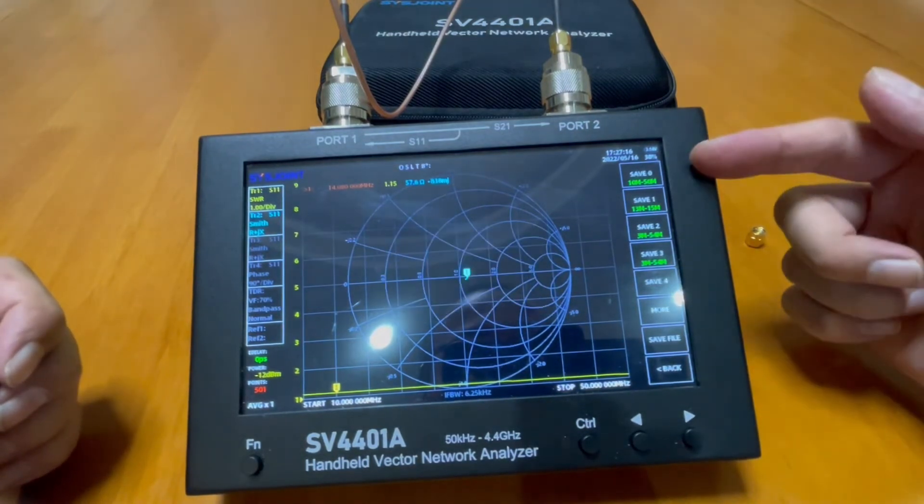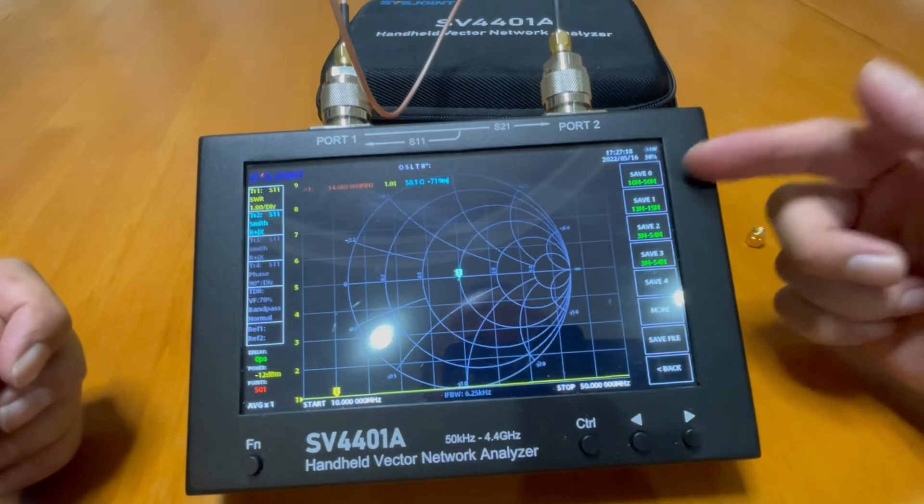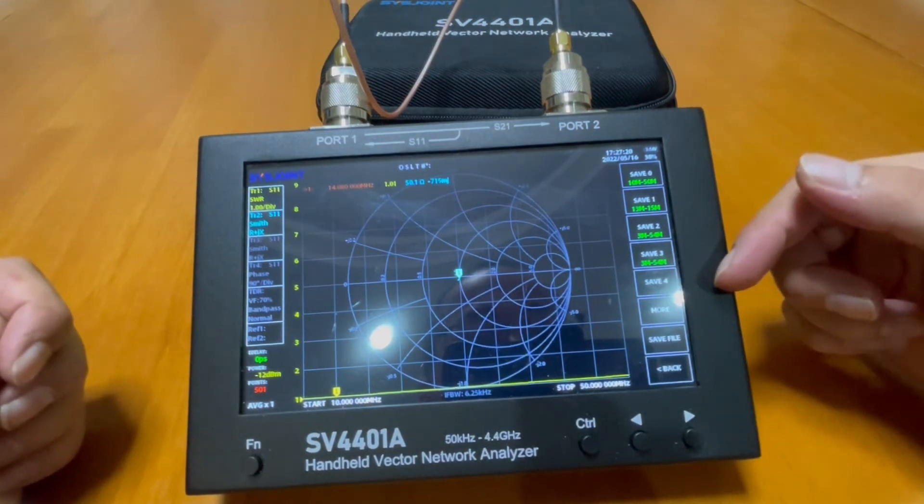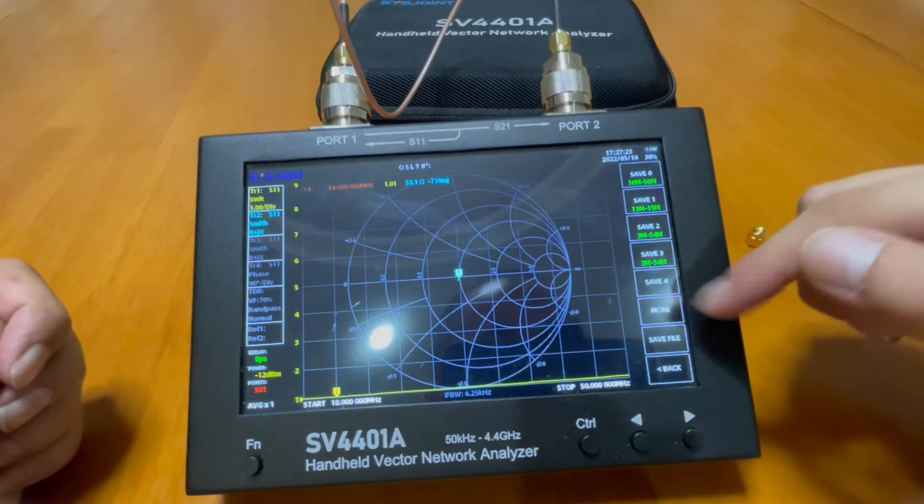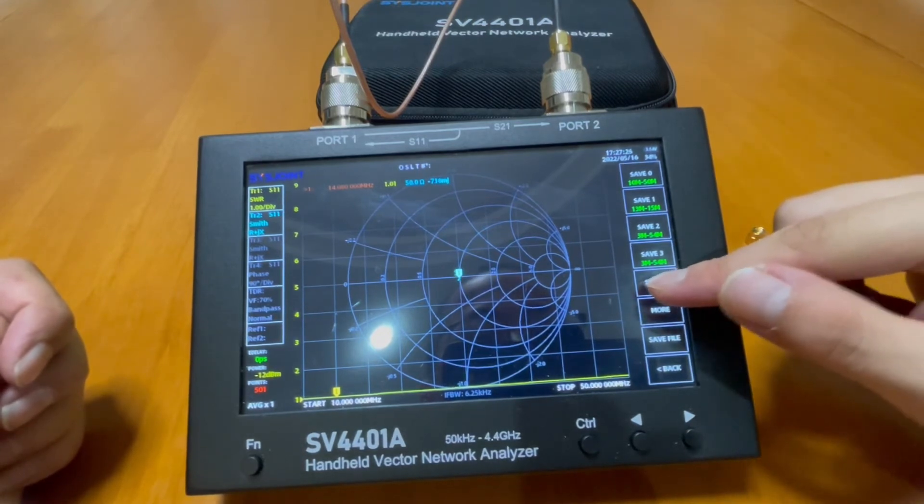What you're going to do is save the calibration result in one of the channels. Let's say we put the result to channel 4.